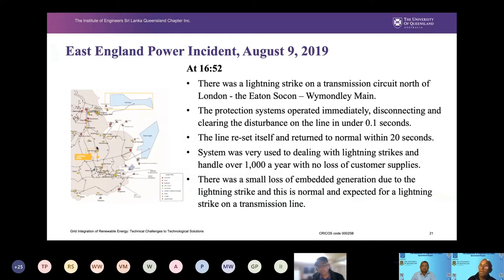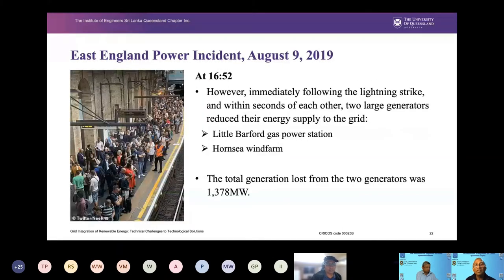But however, there were so many lightning strikes, and the system was designed to cope with a number of lightning strikes. However, in this particular incident, due to a coincidence of incidents, there was a loss of not only wind power generation, but also a small loss of so-called distributed generation, and that started all this chaotic event in the system.